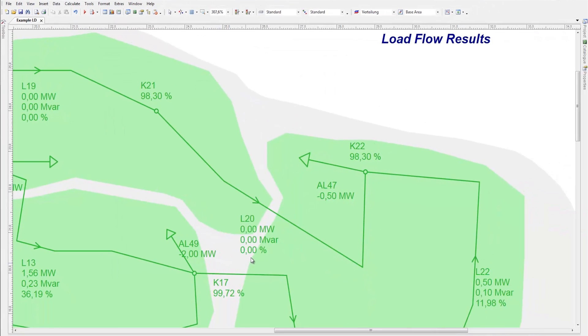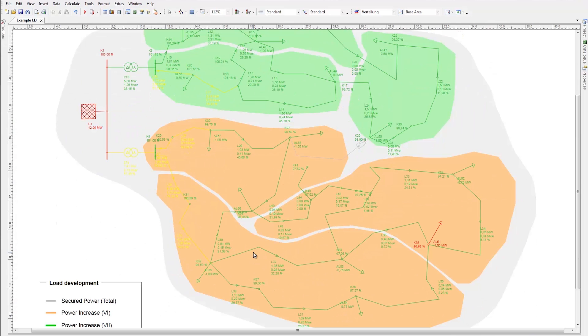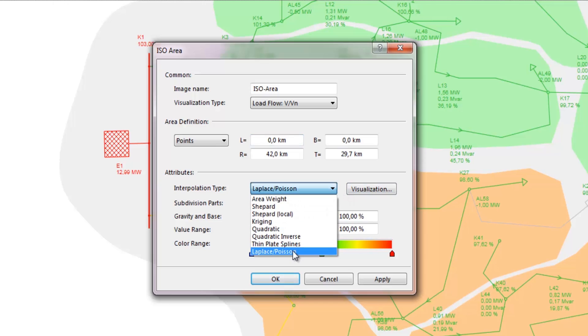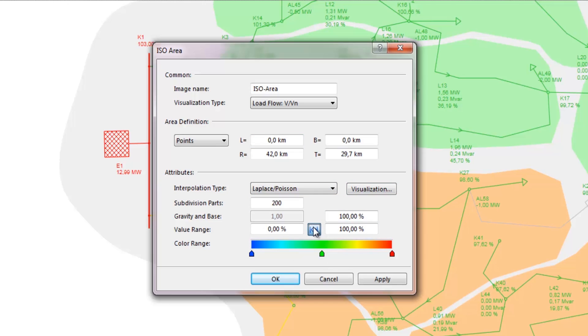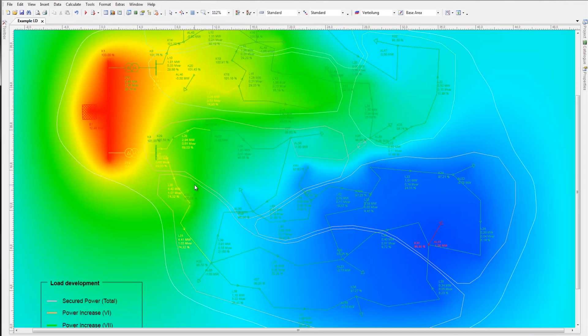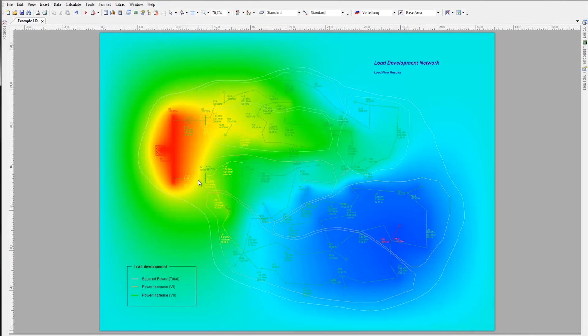After performing a load flow calculation, PSS SINCAL provides the ISO area, a useful tool for visualizing the results. Click Tools, ISO area to open the dialog box. Select Load Flow V/VN under Visualization Type. Adjust the color range and other settings, then click OK. This powerful visualization tool gives the planner an immediate visual overview of the power consumption across the network, useful especially for large networks. In this example, network areas displaying under-voltages can clearly be seen in blue. PSS SINCAL's visualization tools give you the ability to highlight critical elements or operating states in a flexible, user-defined way.